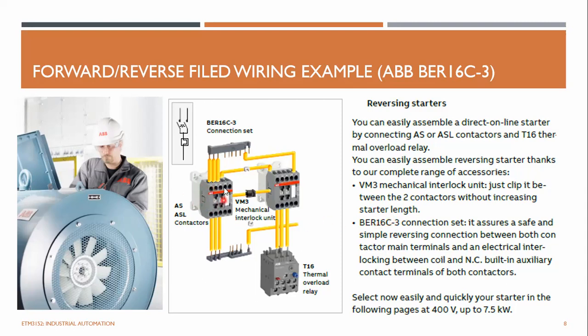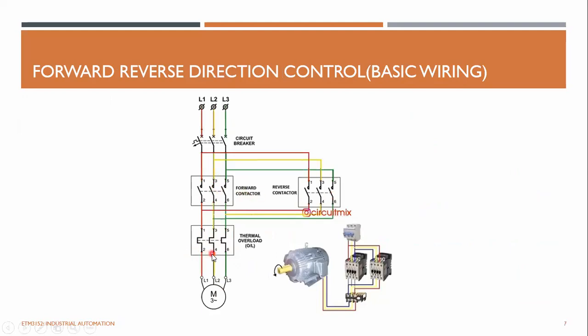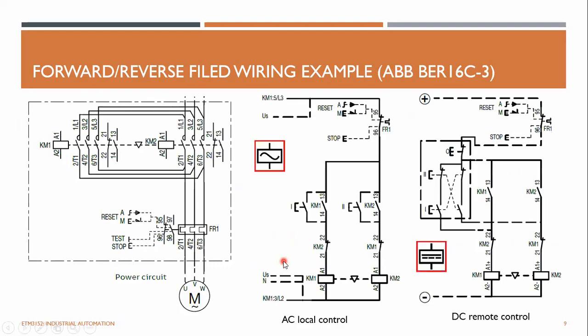So this is a direct online starter, and it goes to the thermal overload. And you can use this reverse starter kit. This is the forward starter kit, and this is a mechanical interlock, which means if this is pressed, this one is not allowed to be pressed, and if this is pressed, this one is not allowed to be pressed. So these are mechanically interlocked, not allowing both to operate simultaneously. This is the forward contactor, and this is the reverse contactor, and it goes to the thermal overload, like I explained here, right? Forward, reverse, and thermal overload, right? See.